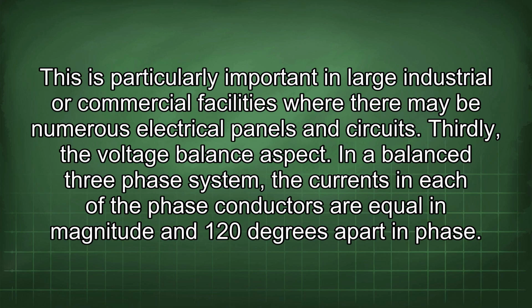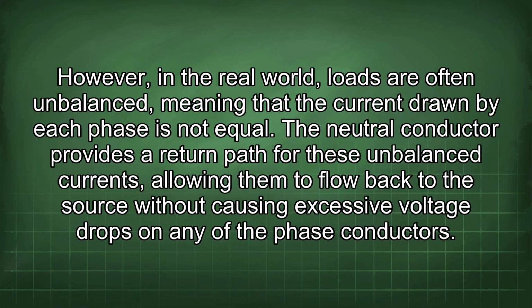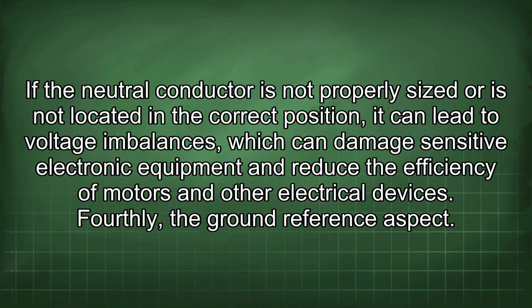Thirdly, the voltage balance aspect. In a balanced three-phase system, the currents in each of the phase conductors are equal in magnitude and 120 degrees apart in phase. However, in the real world, loads are often unbalanced, meaning that the current drawn by each phase is not equal. A neutral conductor provides a return path for these unbalanced currents, allowing them to flow back to the source without causing excessive voltage drops on any of the phase conductors. If the neutral conductor is not properly sized or is not located in the correct position, it can lead to voltage imbalances, which can damage sensitive electronic equipment and reduce the efficiency of motors and other electrical devices.